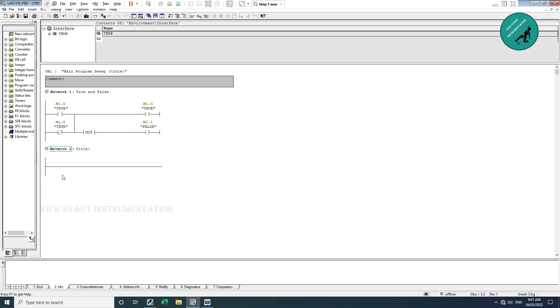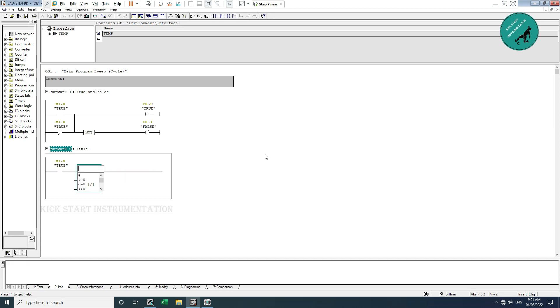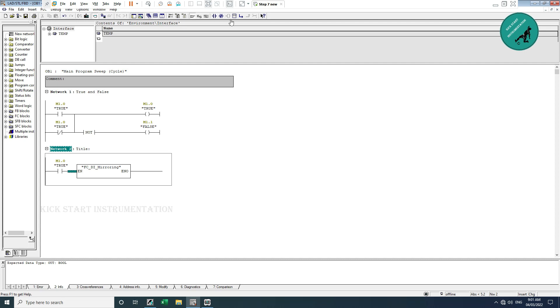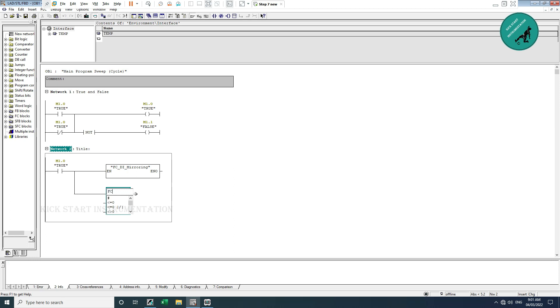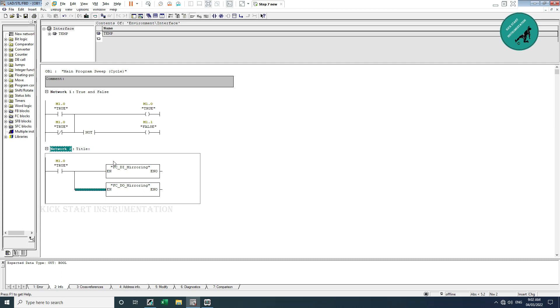I insert a new network. If TRUE, it will call the DI mirroring which is FC1. Then I connect FC2 which is DO mirroring. The reason for using True or False here is: in the future, if you want to diagnose only the digital input signals, you can add an NC contact and make it False, which will block the DI mirroring from executing while other logic continues. So this enables selective diagnosis.